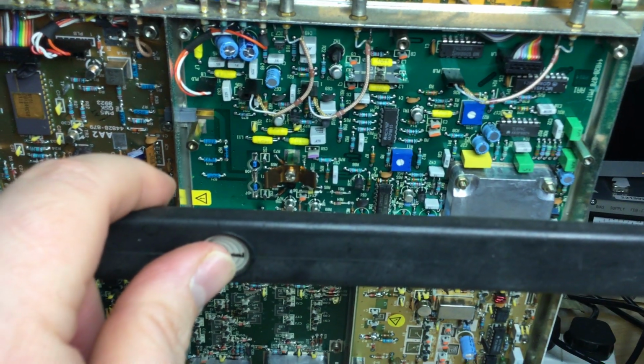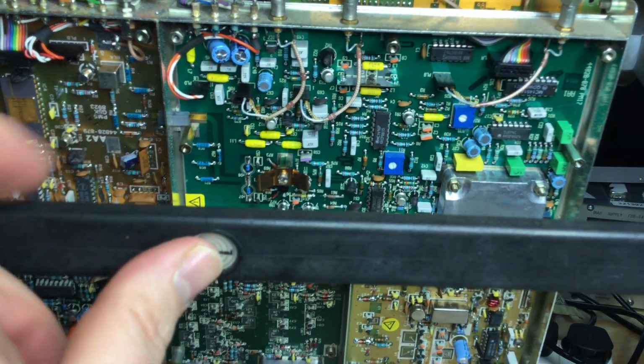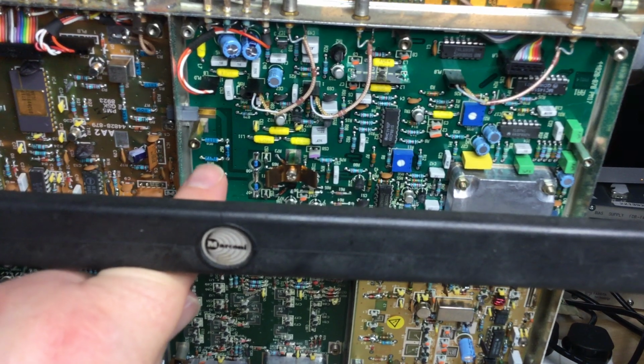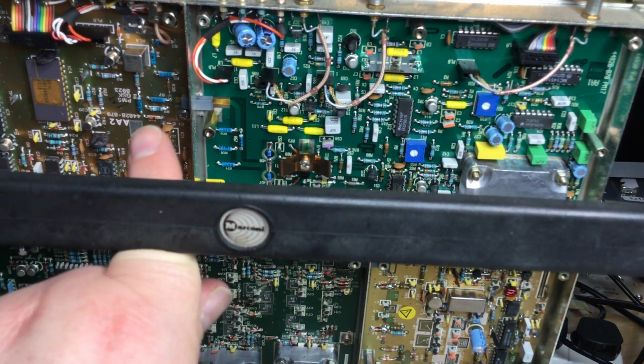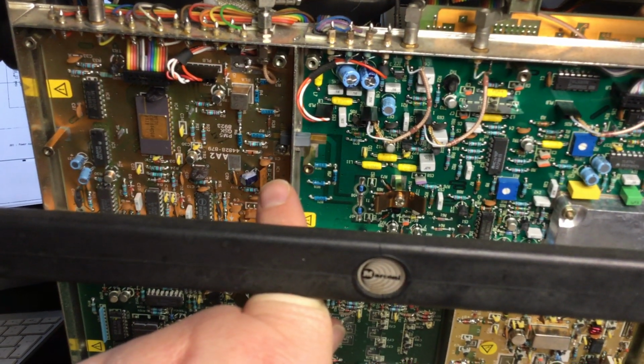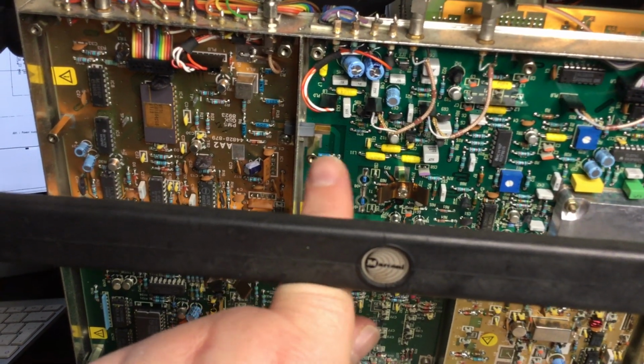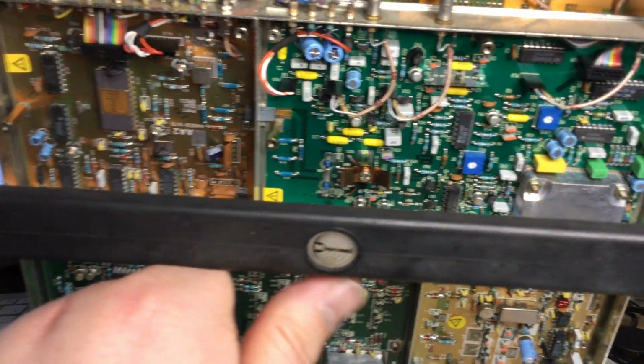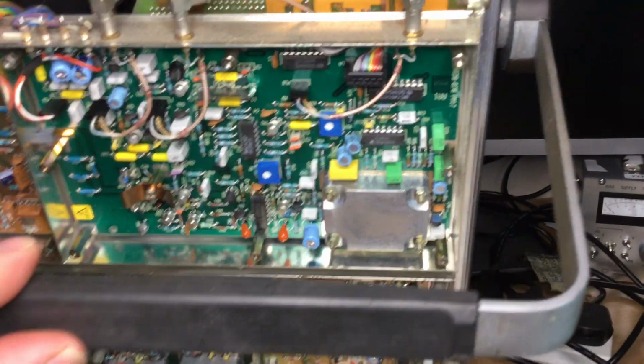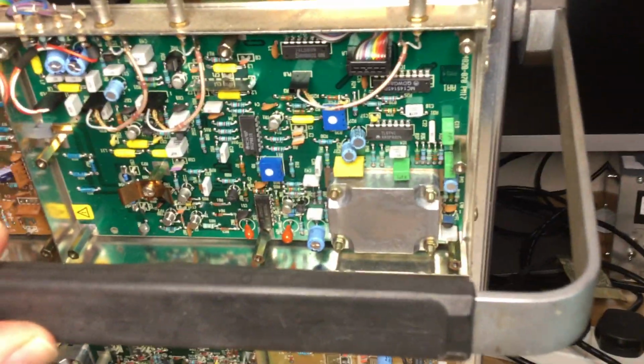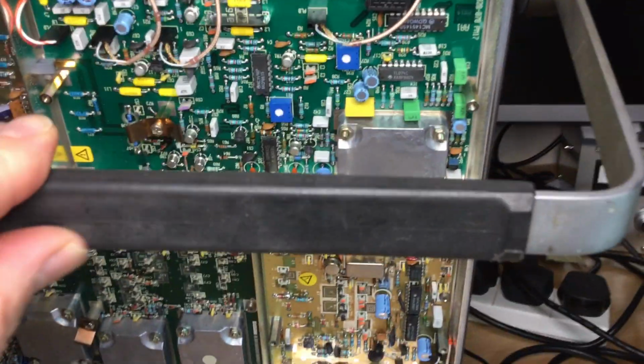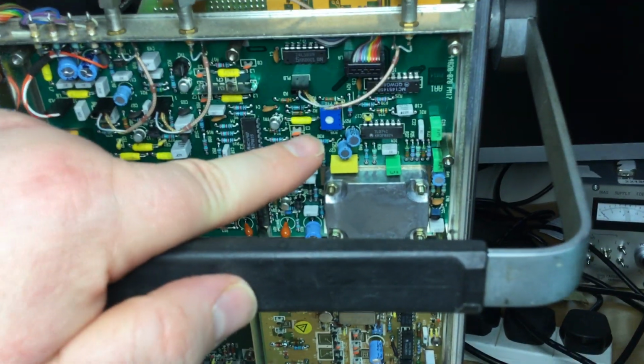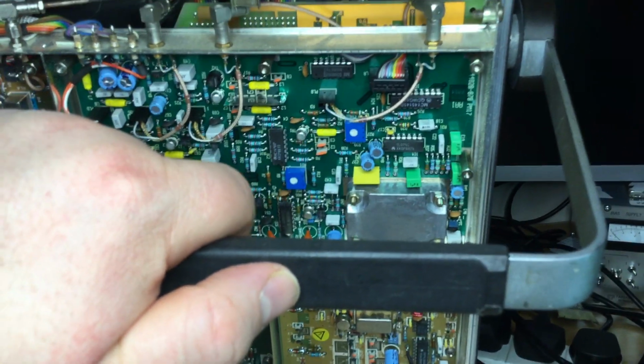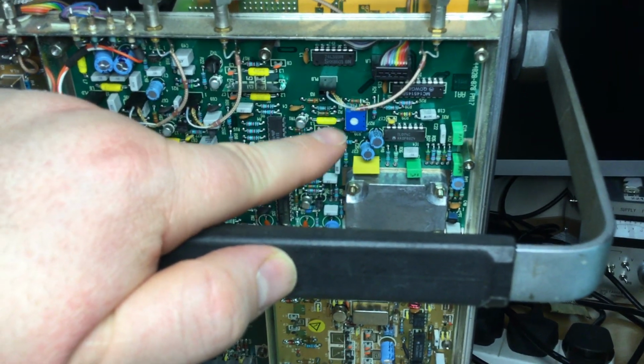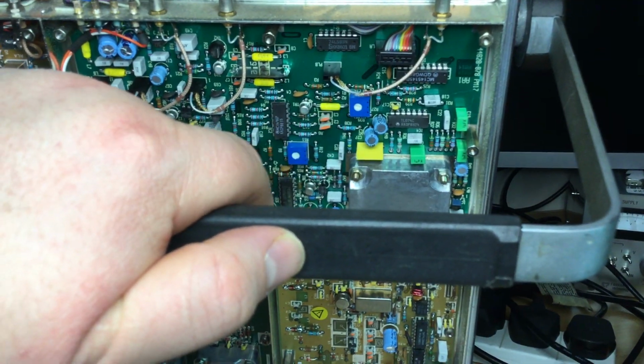And we can see that already there's a pi attenuator there, an RF signal pi attenuator, where it gets passed off to the frequency counter section as well. So it's obviously sharing the same TX signal that's coming in from the RF attenuator section. And then on top of that as well, we've got potentiometers that we can see here, which will then in the service manual allow you to adjust the setting or the calibration of that.